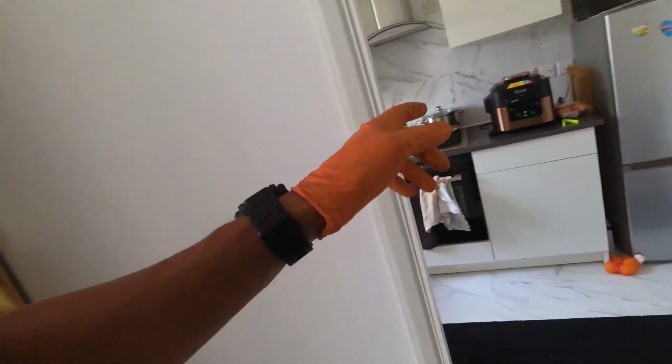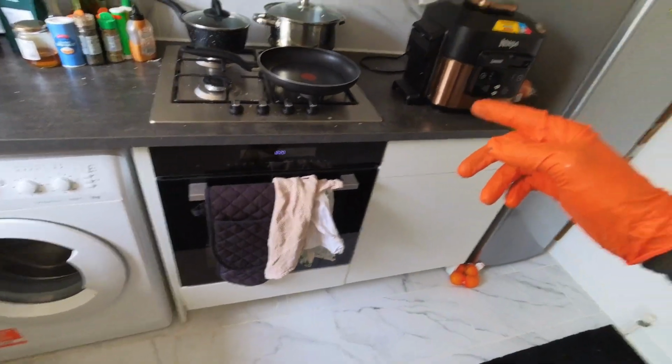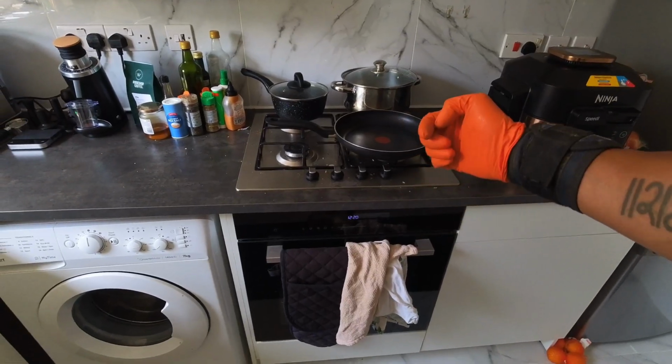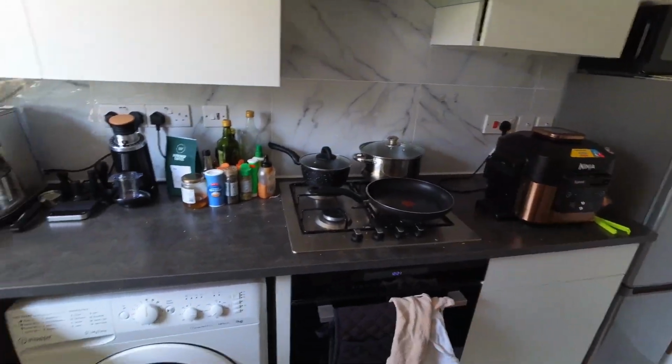And this is the one, if you remember, when I had to redo the pipework for this hob, because I think the kitchen fitter who fitted it put it on a hose, and can't have that on hose. I think you can on certain manufacturers. It depends if they state you're allowed it or not, but if it doesn't state, then it's got to be hard pipe. This is the one where the gas pipe was in the wall, and then there was a bayonet literally just coming out the wall, and when I tried twisting it, the whole thing twisted. So then I had to chase out part of the back wall. I had to get onto the copper pipe, and I managed to solder a street elbow coming out and then up and then into the hob.